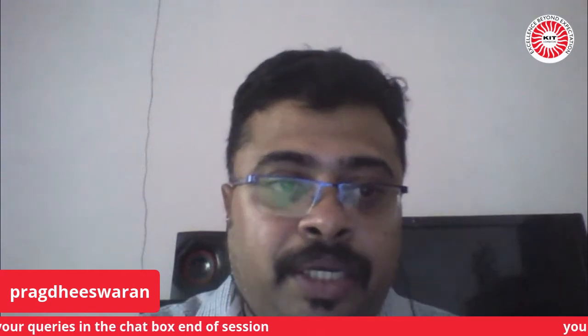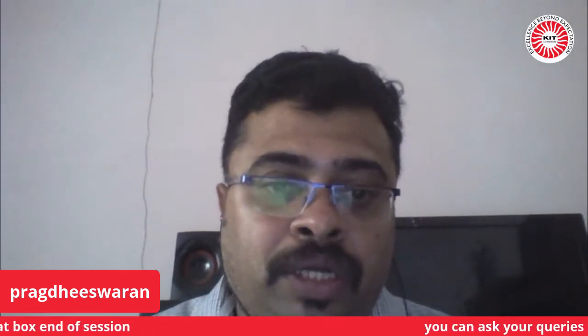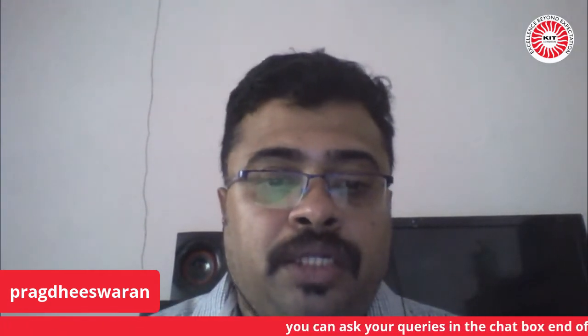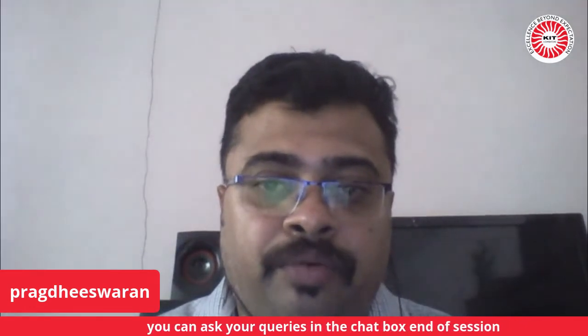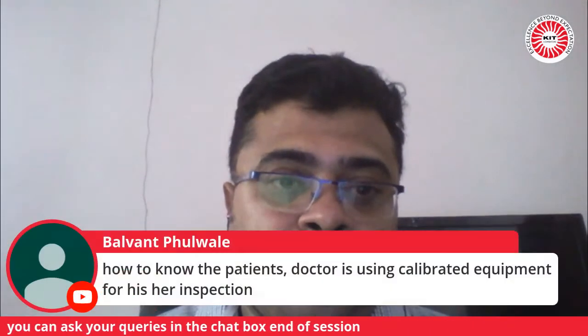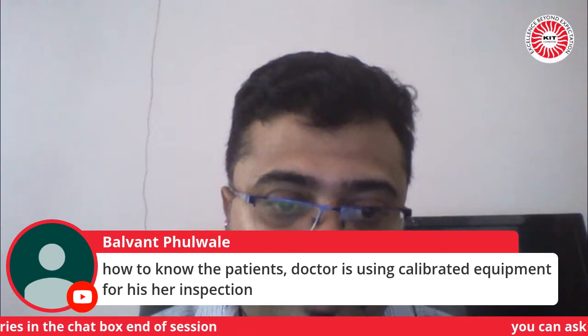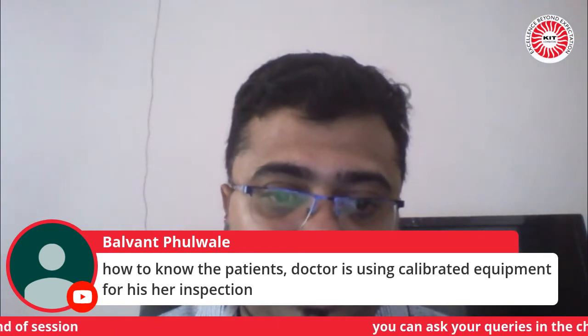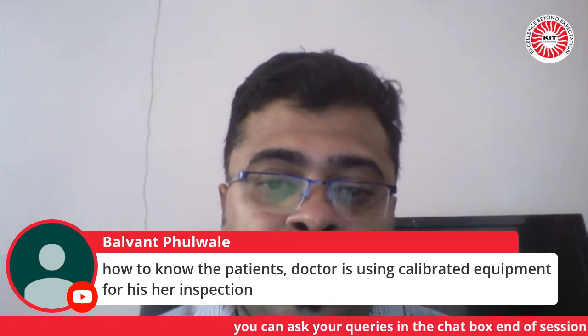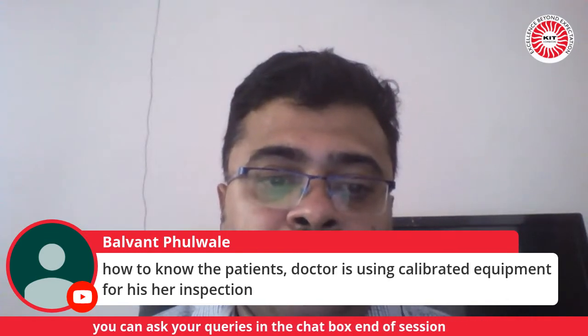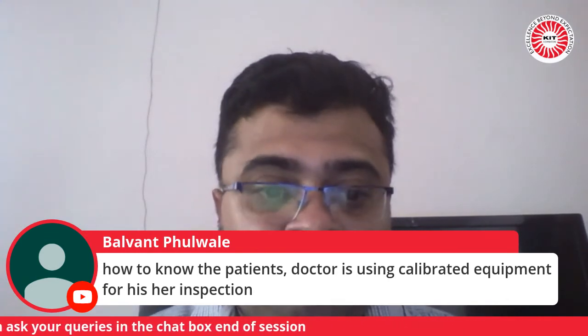I attach with the equipment a quality certificate saying it is tested as per IEC, for these many parameters, along with my CE standard certificate or CDSCO standard certificate. This is what the quality certificate is expected to be for every equipment you buy as a biomedical engineer. But how does the patient or doctor know the equipment being used for inspection is calibrated?